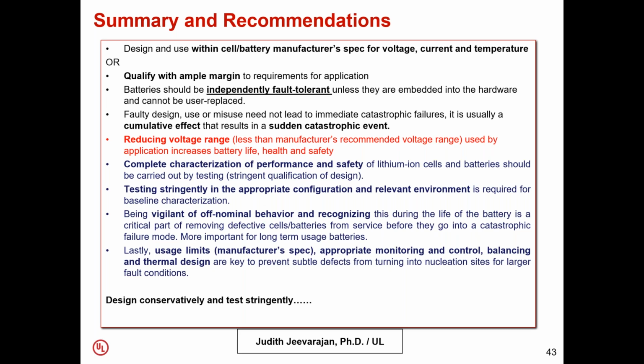Batteries should be independently fault tolerant unless they are embedded into the hardware, where the device can provide additional levels of control. Faulty design, use, or misuse need not lead to immediate catastrophic failures; it usually is a cumulative effect that can result in a sudden catastrophic event.